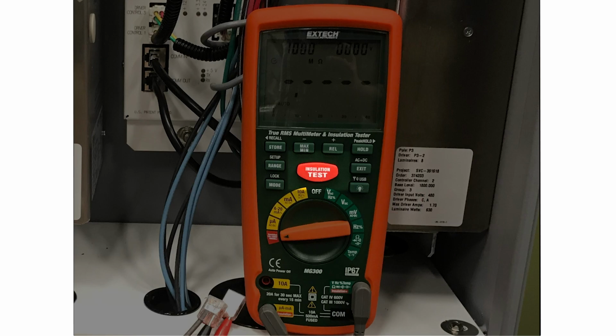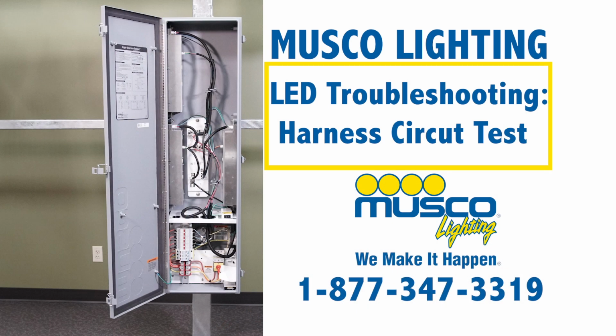The reading should be high, 100 mega ohms or better. If you get less than 100 mega ohms, this may indicate an insulation issue with the fixture circuit. The MUSCO technical specialist will be able to walk you through further testing if needed.